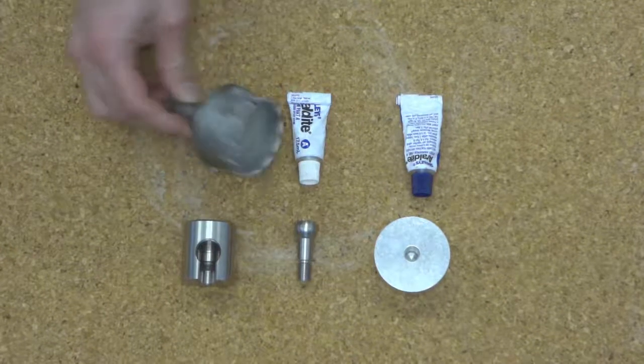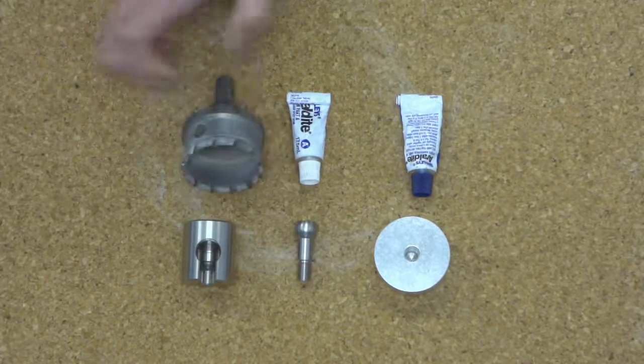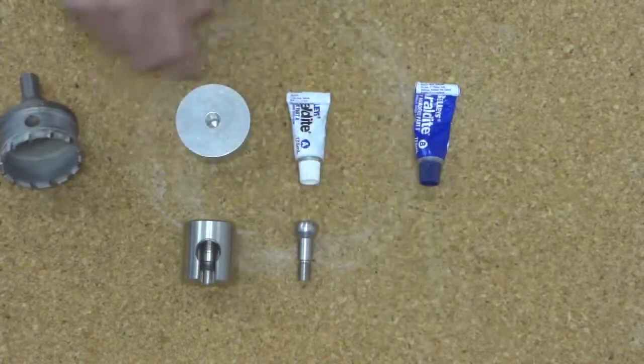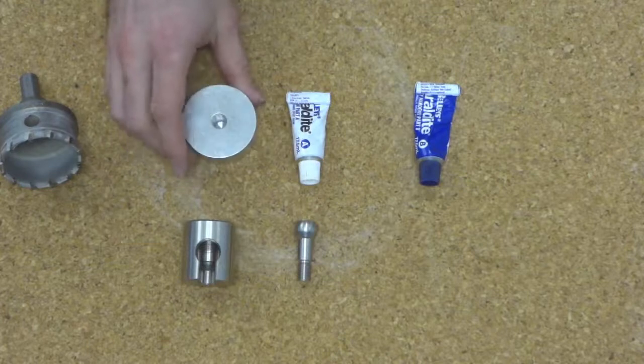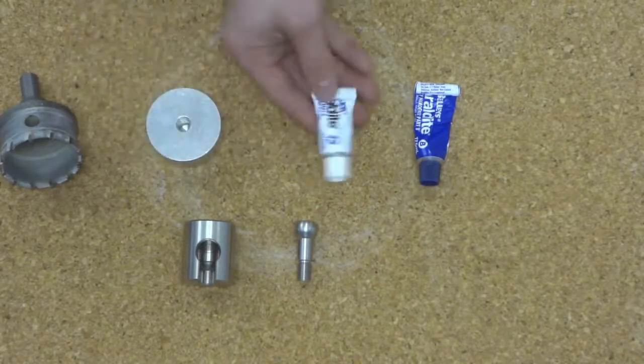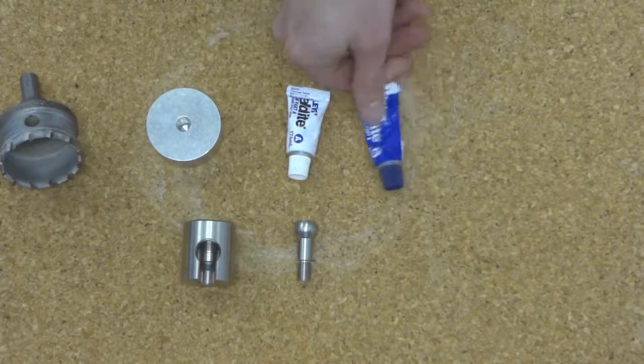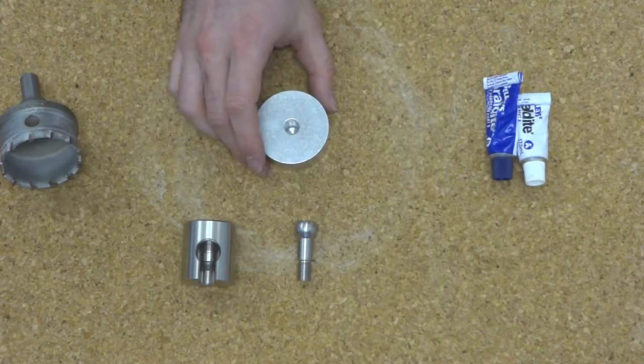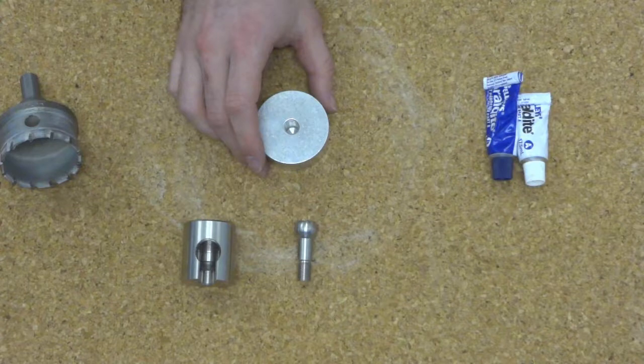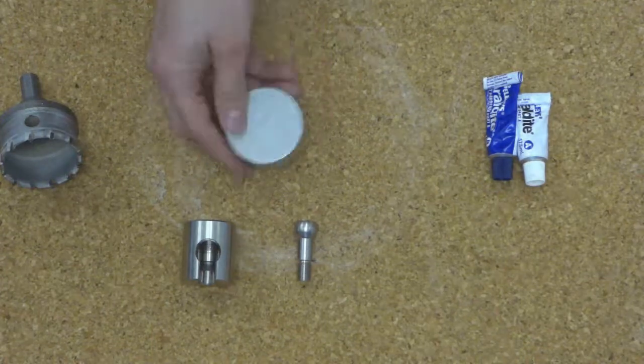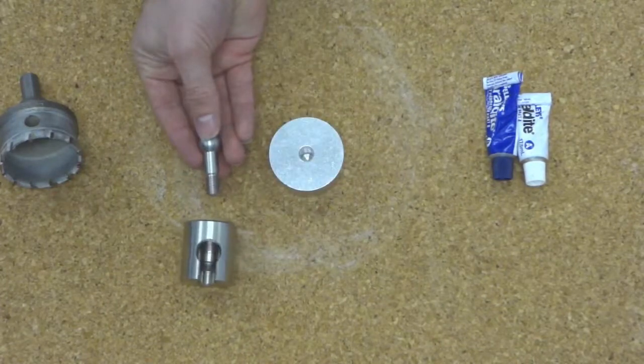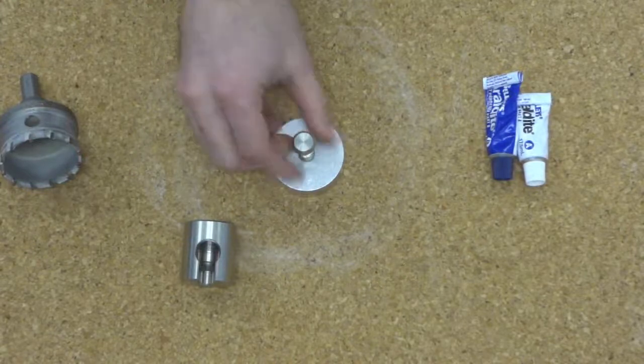So once we've drilled our hole around we'll have a circular area which should have the exact same diameter as the face of the test disk. So this one's 50mm so it would need to be 50mm internal diameter. This can be glued in place using an epoxy which is generally suitable. If you're in a hurry it is possible to use something like a super glue but that's only if the coating is non-porous otherwise it'll absorb the super glue and may appear stronger than it actually is. So once we bond our surface we'll then need to leave it overnight for epoxy or the super glue you can test in about an hour.